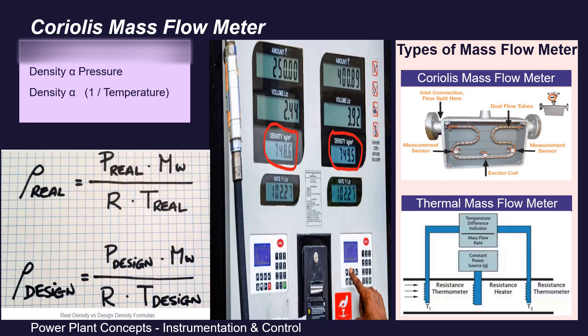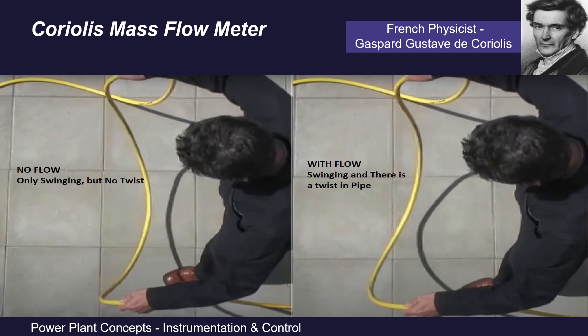Now if we need direct mass flow measurement instead of doing all these conversions in the DCS, we may use mass flow meters. From these discussions it is clear that mass flow meters must not only measure the flow volume but also measure fluid density so that they can directly give readings in terms of mass flow.